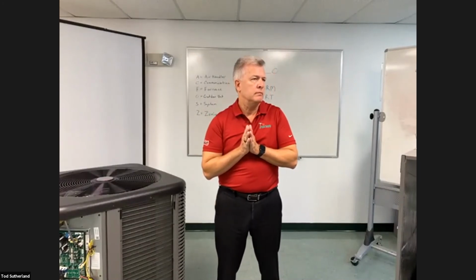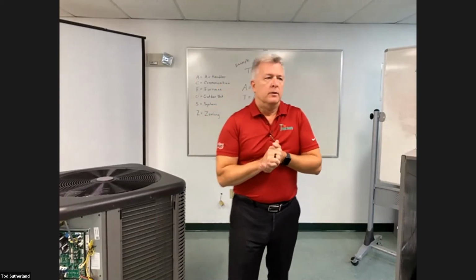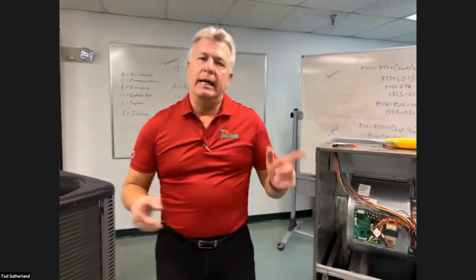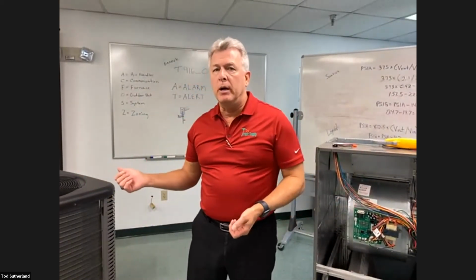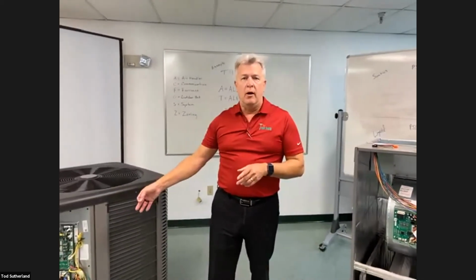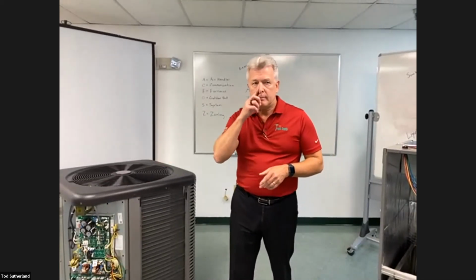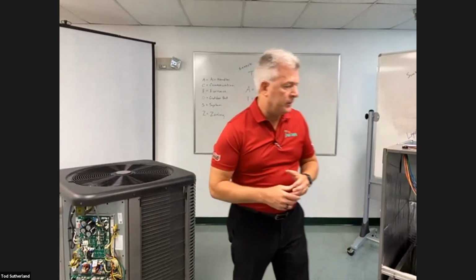Okay. All right, let's move on to the questions. Somebody will have to read them out because I can't see them. Hensley's question is, with the older Prestige system, it's normally 0.6 volts DC from the control board to the motor. Is it the same with the new ones? No. No, and it wasn't DC, it's AC voltage. Well, again, are you talking about the indoor blower motor or the outdoor motor? Because on the outdoor motor, on the older Prestige systems, you also had a blue and yellow wire that you could jumper 24 volts to and get the fan motor running. But no, both of these motors are just like the variable speed motors that you have on your RHMV air handler, where they're AC voltage, not DC voltage. He says indoor blower. Yeah, no, they're AC voltage.